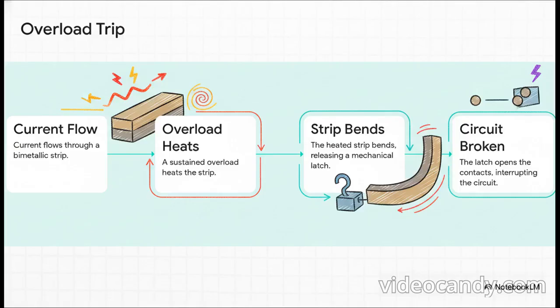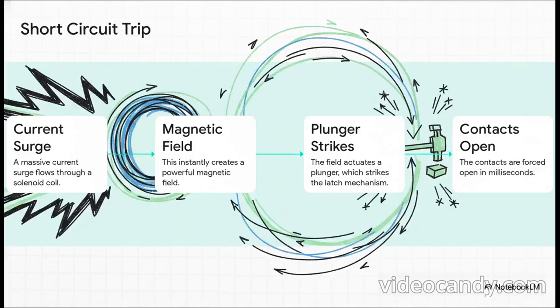After maybe a few seconds or even a couple minutes of this sustained overload, it finally bends far enough to pop a latch and click, the power's cut. It's patient. It's designed to ignore small, harmless little power fluctuations. The short circuit protection, on the other hand, is all about speed.